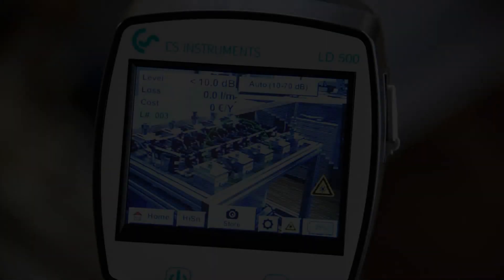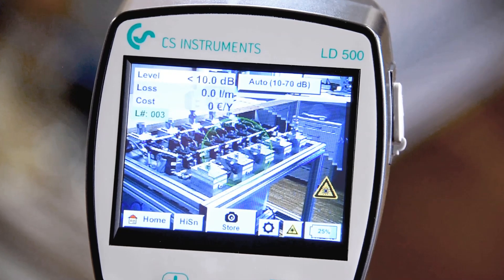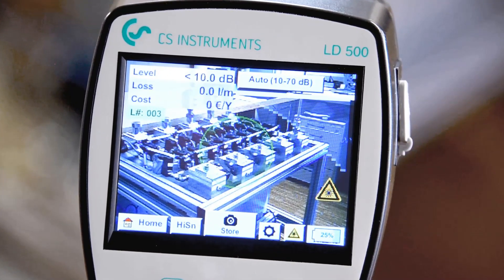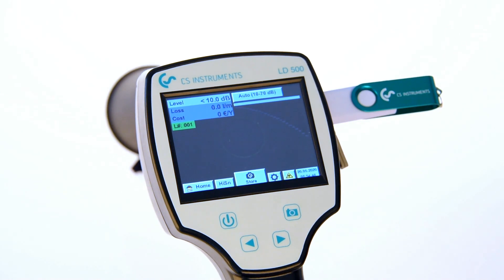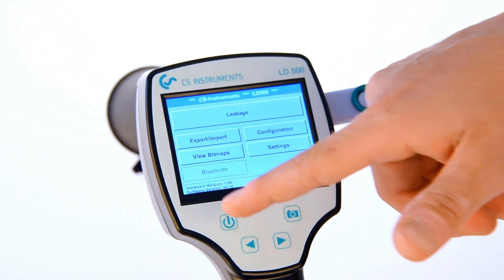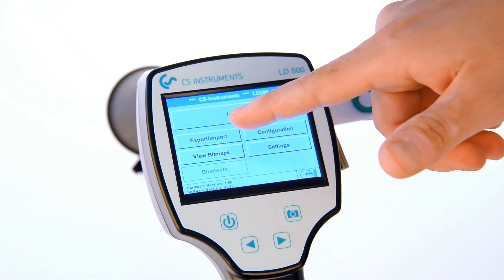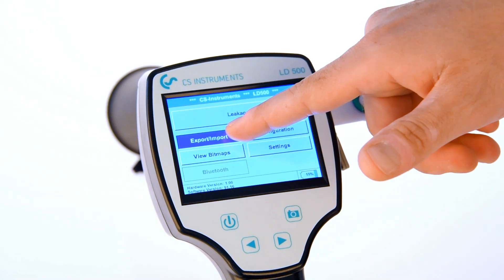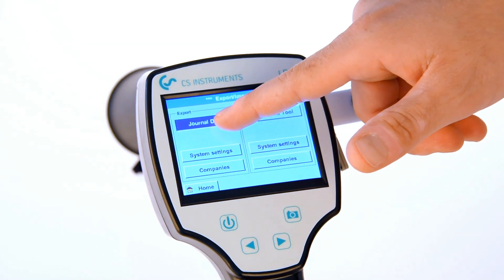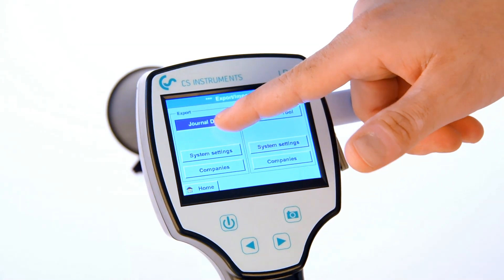After the repair of a leak, the LD500 or LD510 can be used to verify the leak tightness. After the air audit is completed, all saved data can be exported to a USB stick. The start and end points of each export are freely selectable.